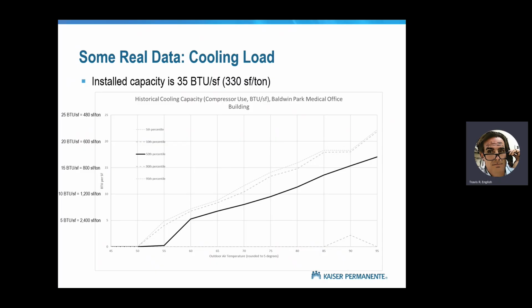That's how big the units are. Now, in the 95-degree historical data, we did have 10% and 1% of the data that got up to about 22.5 BTU per square foot or 550 square foot per ton. But the average at the 95-degree day is 17.5 BTU per square foot or 700 square foot per ton. That's where we're actually at in the 95 hour. And that's about half of the installed capacity. So compared to the historical load, the unit is basically oversized by double. And I'm going to talk more about that in a minute.